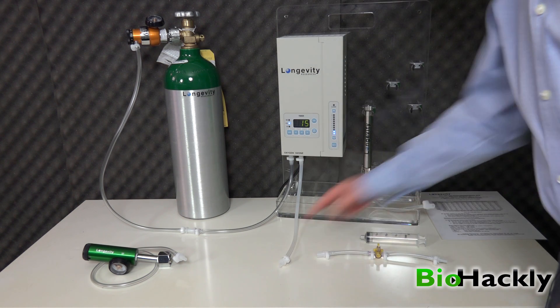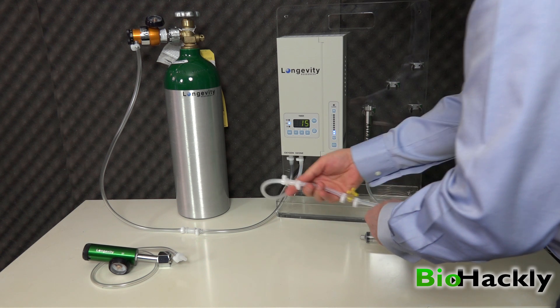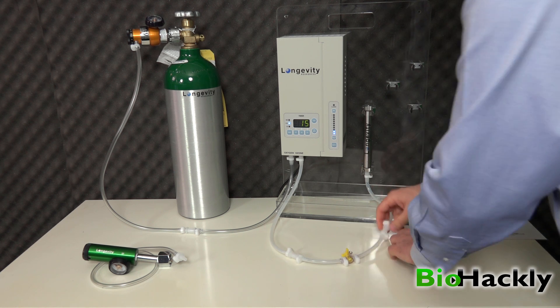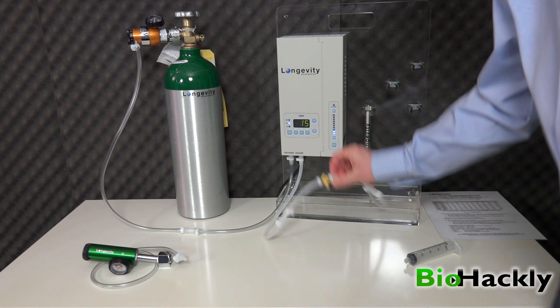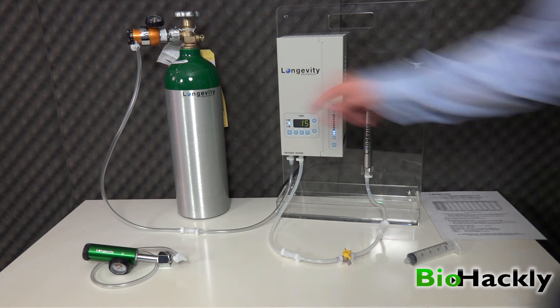First I'm going to connect the clear oxygen tank hose to the input oxygen line on the ozone generator. Then I'm going to take the ozone out silicone line here and connect that to the luer lock valve — it only goes in one way, it only fits one side and won't plug into the other. From here I'm going to plug this into the ozone destruct unit, which will allow me to turn everything on. It's going to be generating ozone right through the pipe, and as long as I have it set in that position it won't allow any ozone to escape — it continues the flow and turns it back into oxygen.